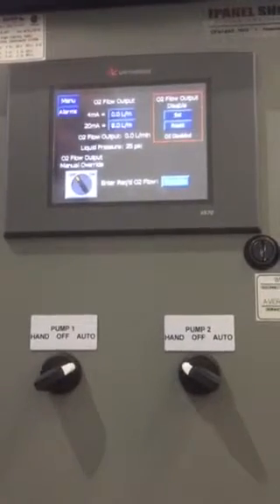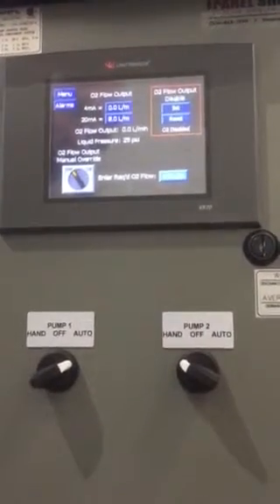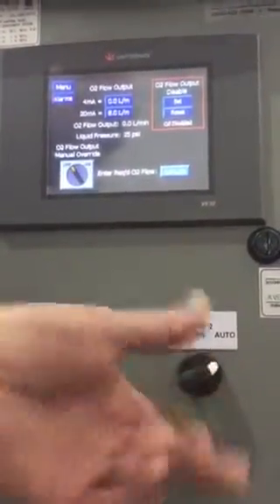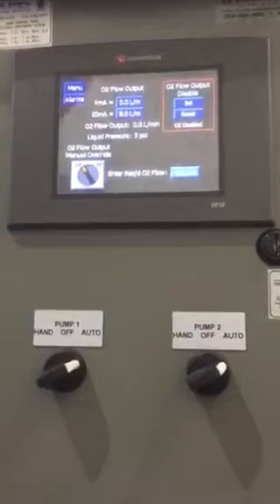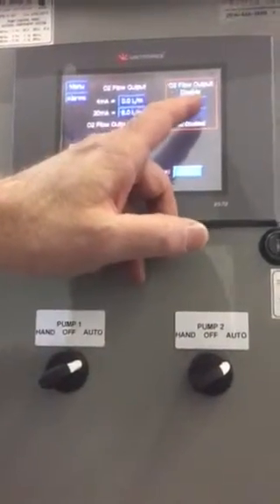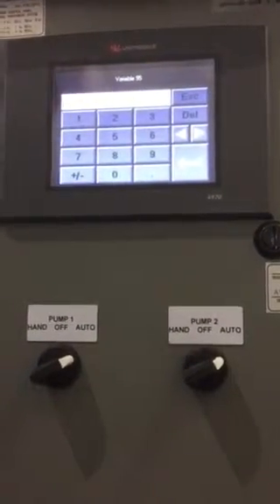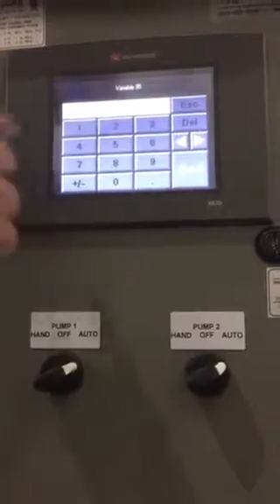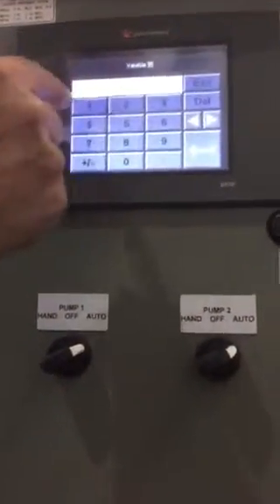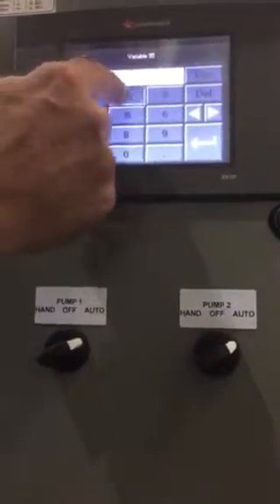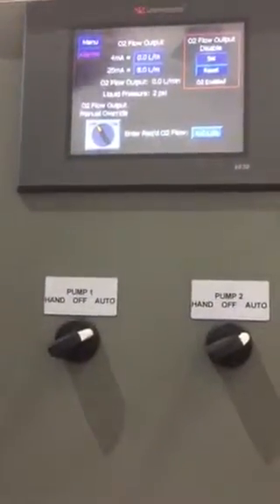The unit is inoperative right now. Even though it's pumping, it'll transfer liquid, but it won't oxygenate anything. But in normal operation in auto mode, everything is disabled. If you want to re-enable it, you have to hit the reset button. What happens is a touch screen comes up, numeric entry, and you have to put a password in and hit enter, and everything's going again.